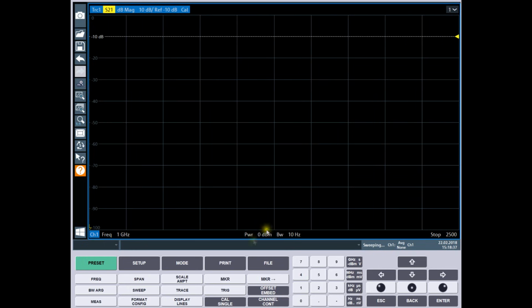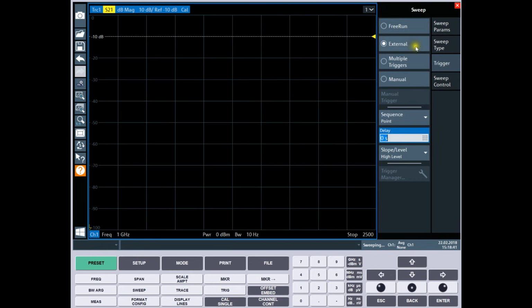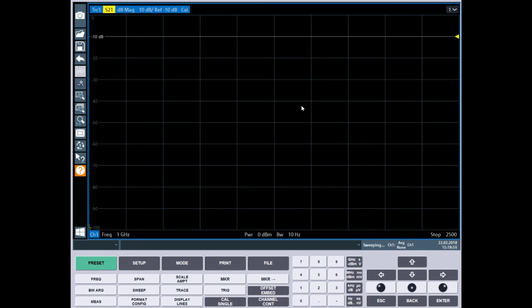And then a few other things I can do here. For example, on the trigger, I have it set to external trigger, and the trigger level when it hits a high level. So I have a signal coming in, which will then trigger per point. You can see I am sequencing it per point. So I can go ahead and let go of the reset on my instrument, and it should start sweeping. So here we go. There we go. And as you can see, there it is. It's beginning to sweep from the top.